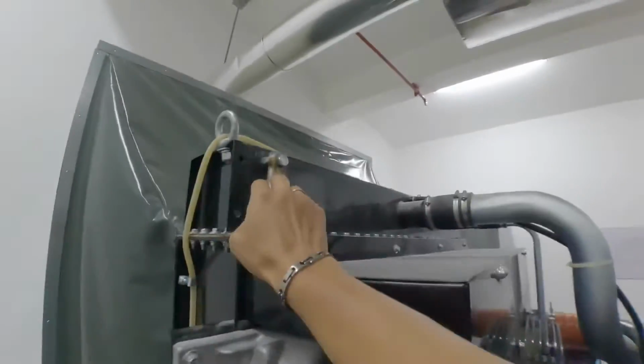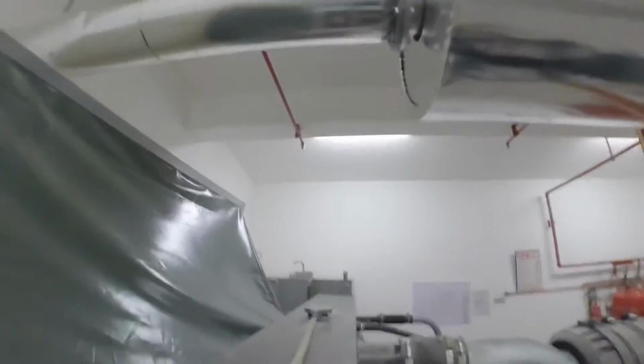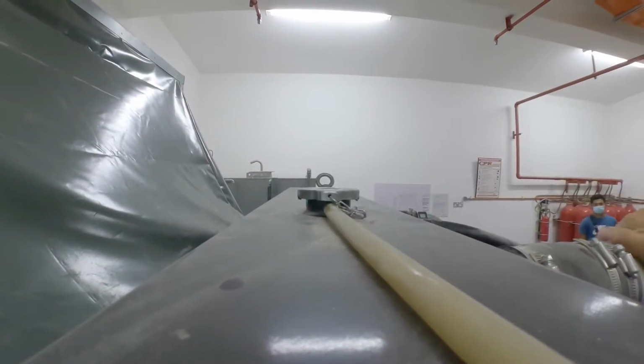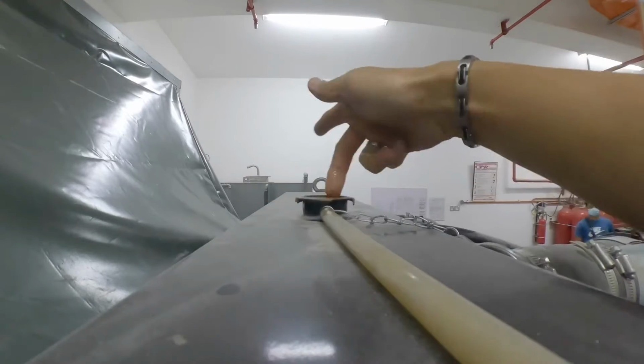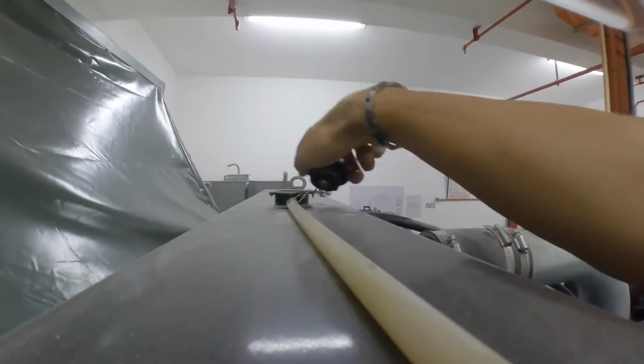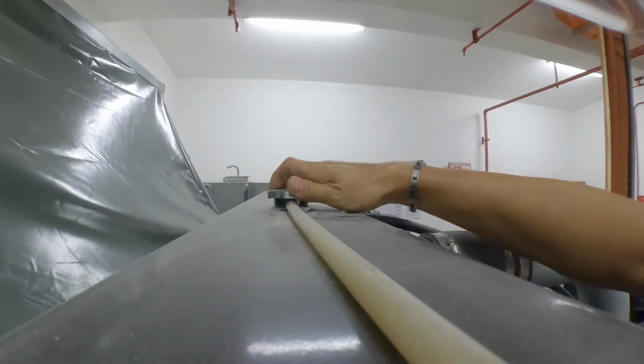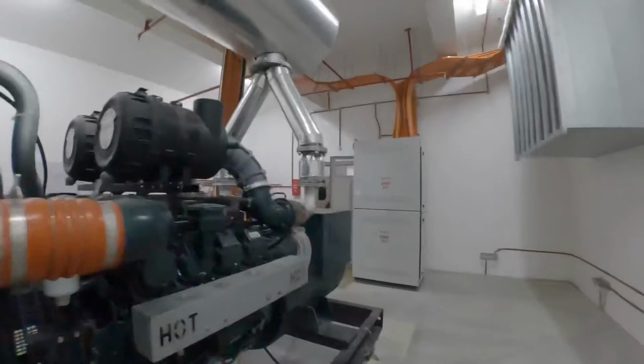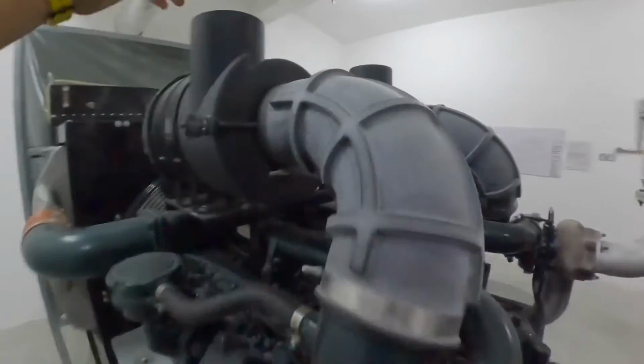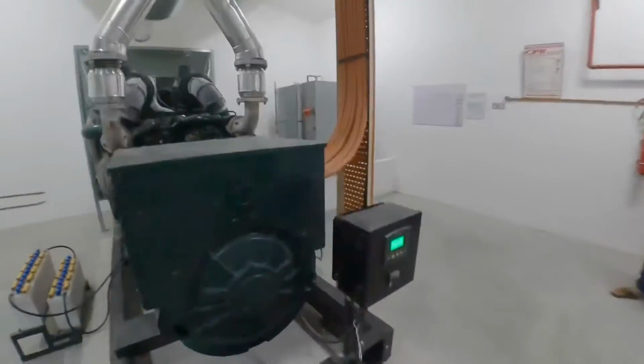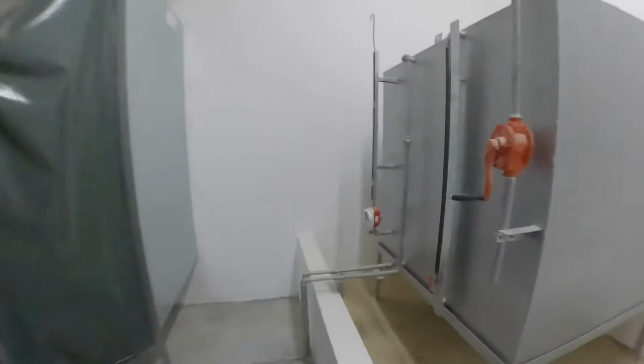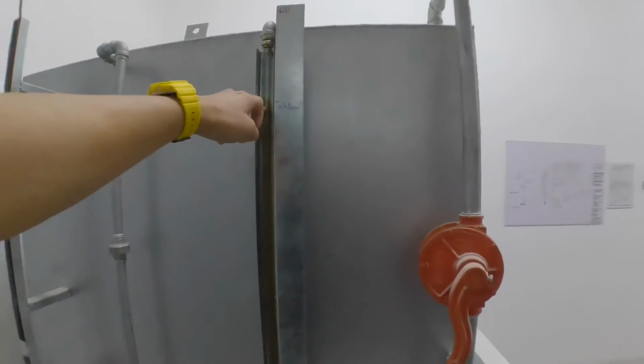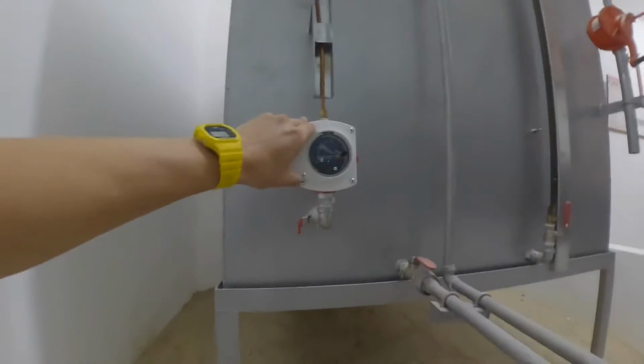And then we have the radiator, and we need to check the radiator water, make sure it's clean. Okay, water is sufficient. Make sure the radiator cap is tightened properly. This is the genset air filter. Next, let us look at the diesel tank. This is the diesel tank. Current level is at 350 liters. And then we have a level indicator alarm.